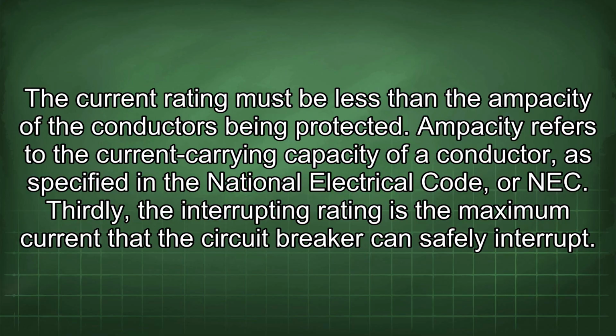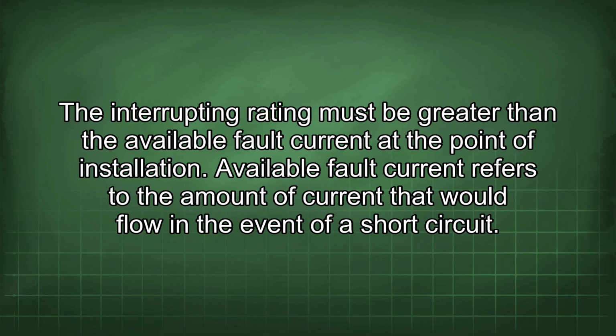Thirdly, the interrupting rating is the maximum current that the circuit breaker can safely interrupt. The interrupting rating must be greater than the available fault current at the point of installation. Available fault current refers to the amount of current that would flow in the event of a short circuit.